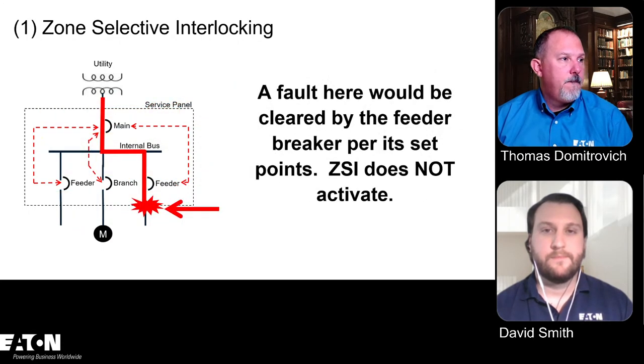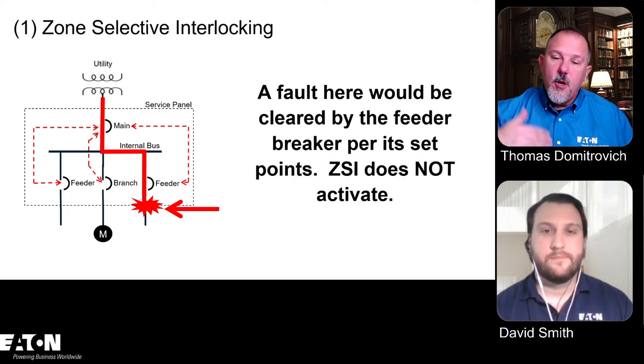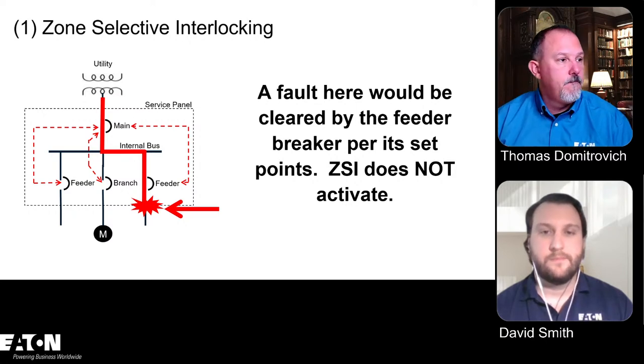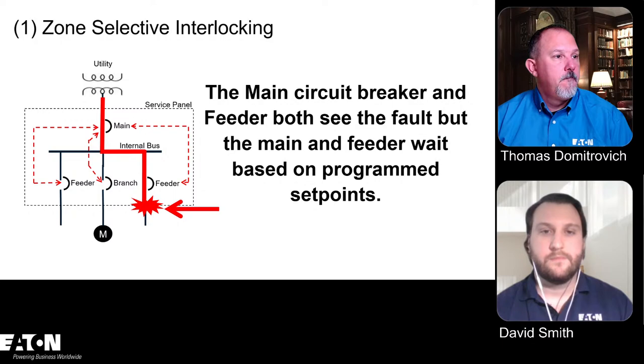And what this is showing you is that for a fault outside of the zone of protection, ZSI sees the same amount of current going in, the same amount of current going out. Both of these devices see the fault, and both of them will go based upon their programmed set points, whatever they are. And that's all that these slides are talking about.